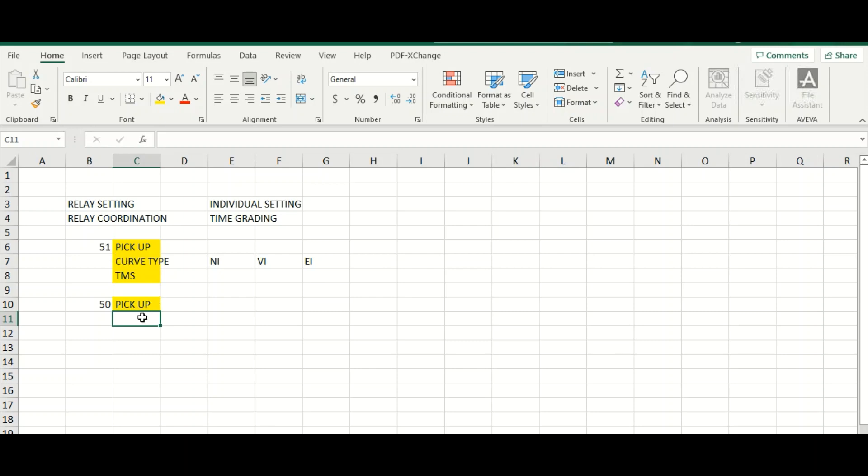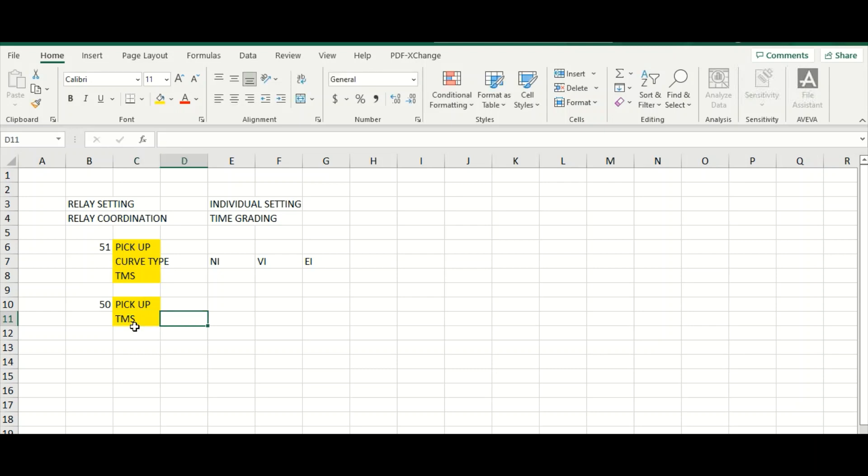Only we need to specify the TMS here, though it is very short time because this element will pick up instantaneously. But please be noted that this relay will not operate instantaneously. Literally, it will take some time, not at time t equals 0. At time t equals 0 it cannot pick up. For this it needs minimum time.